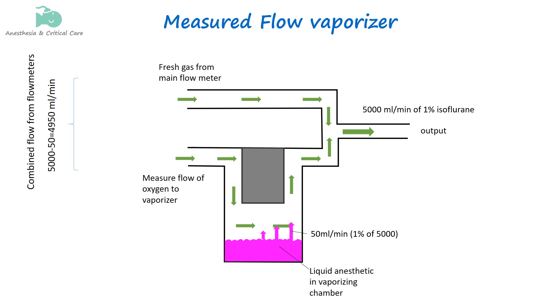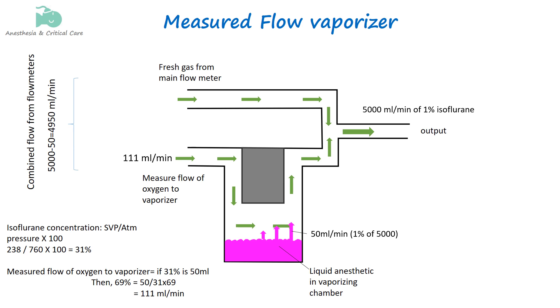The saturated vapor pressure of isoflurane at 20 degrees Celsius is 238 mmHg, which represents 31% of isoflurane. This 50 mL/min is 31% of isoflurane vapor. The remaining 69% of this, or 111 mL/min, is the measured flow of carrier gas or oxygen that must flow to the vaporizing chamber.